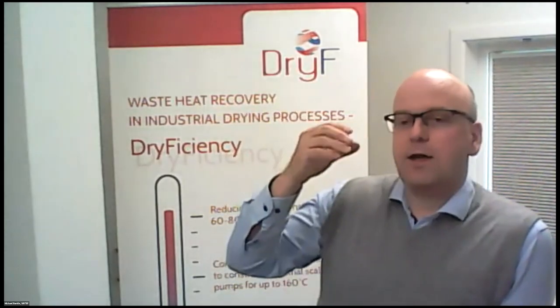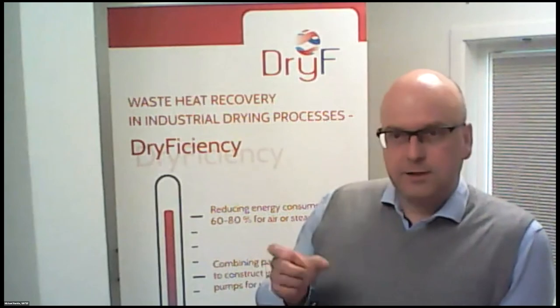Yeah, I think for the open loop, we have a quite narrow field of operation that comes from the characteristic of the turbo machinery, which at the highest pressure level has a quite small acceptable variance in mass flows. So that is really the answer here, that part loads is a problem. For the Scanship demo site, we solved it by having basically two dryers connected to one open loop heat pump system. Otherwise, you basically just have to recirculate steam without doing much work, and that's not the ideal condition. It should match quite nicely, I think, in an industrial site.